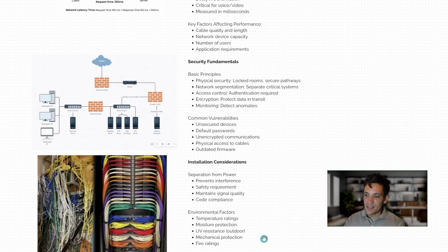Finally, what are some installation considerations when we're talking about networks? Well, the first one is that network cabling is distinct and different to power cabling. You want all your network cabling to be separated from your power cabling. This is a safety requirement. It's mandated by most codes and standards that you can't generally have in the same cable tray an Ethernet cable and a power cable. You can't have a network switch in a distribution board next to live cables.